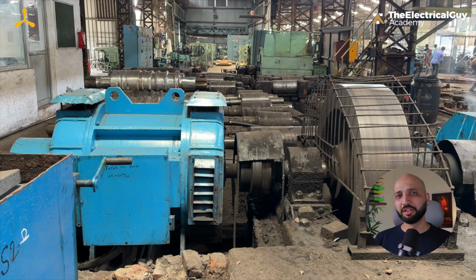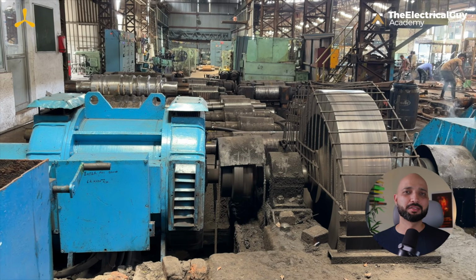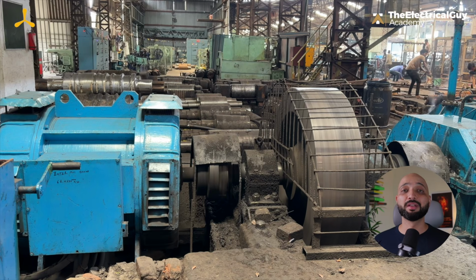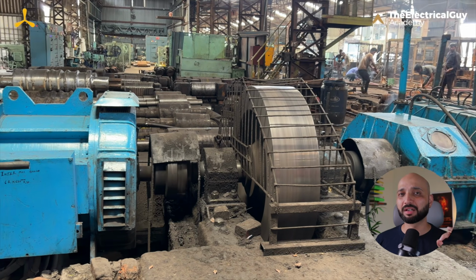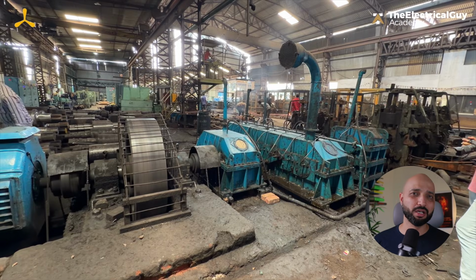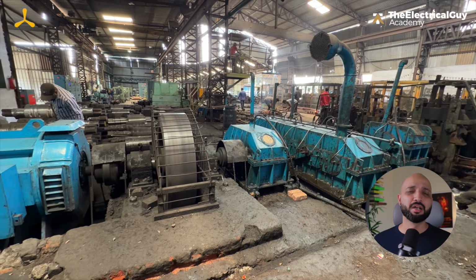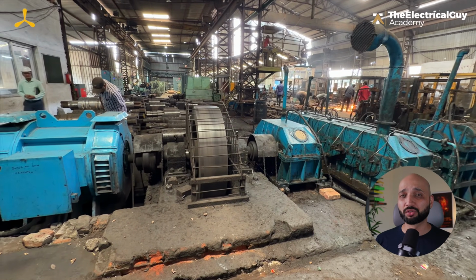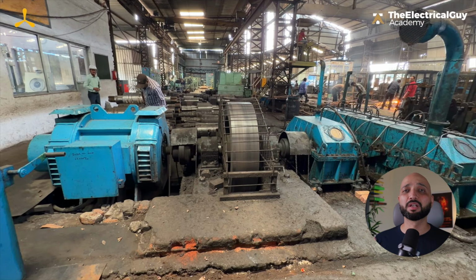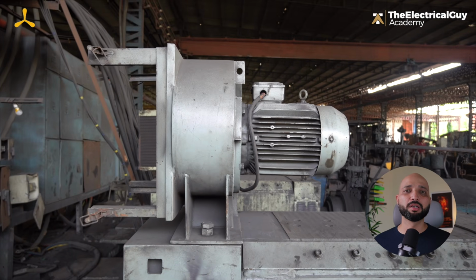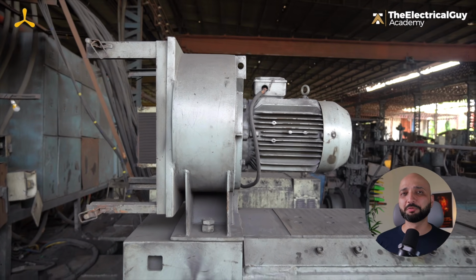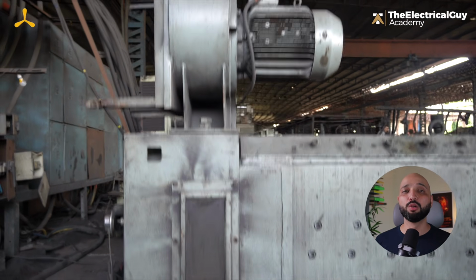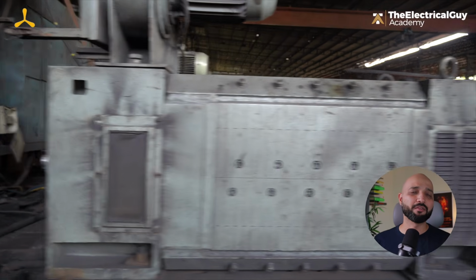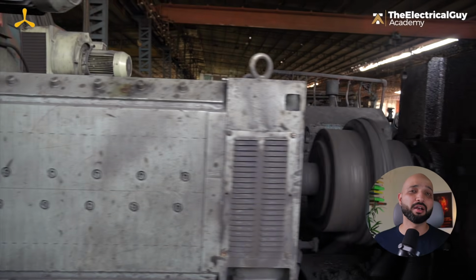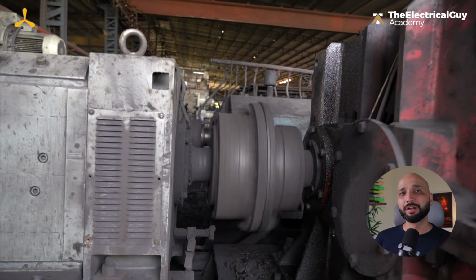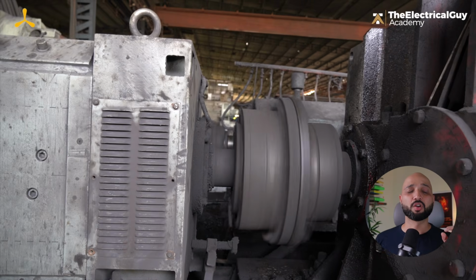Now let's connect these 3 motor types practically. A slip ring induction motor is used when the application needs very high starting torque and has severe load conditions. Roughing mills, heavy rolling stands, crushers, and heavy duty drives are common examples. A DC motor is used where very precise speed control, high torque at low speed, quick reversing and fast dynamic response are required. Reversing mills and older precision rolling mills drives are common examples.